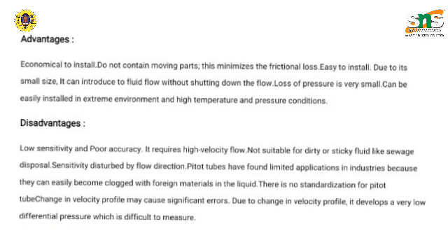Pitot tubes have found limited applications in industries because they can easily become clogged with foreign materials in the liquid. There is no standardization for Pitot tubes. Change in velocity profile may cause significant errors. Due to change in velocity profile, it develops a very low differential pressure which is difficult to measure.